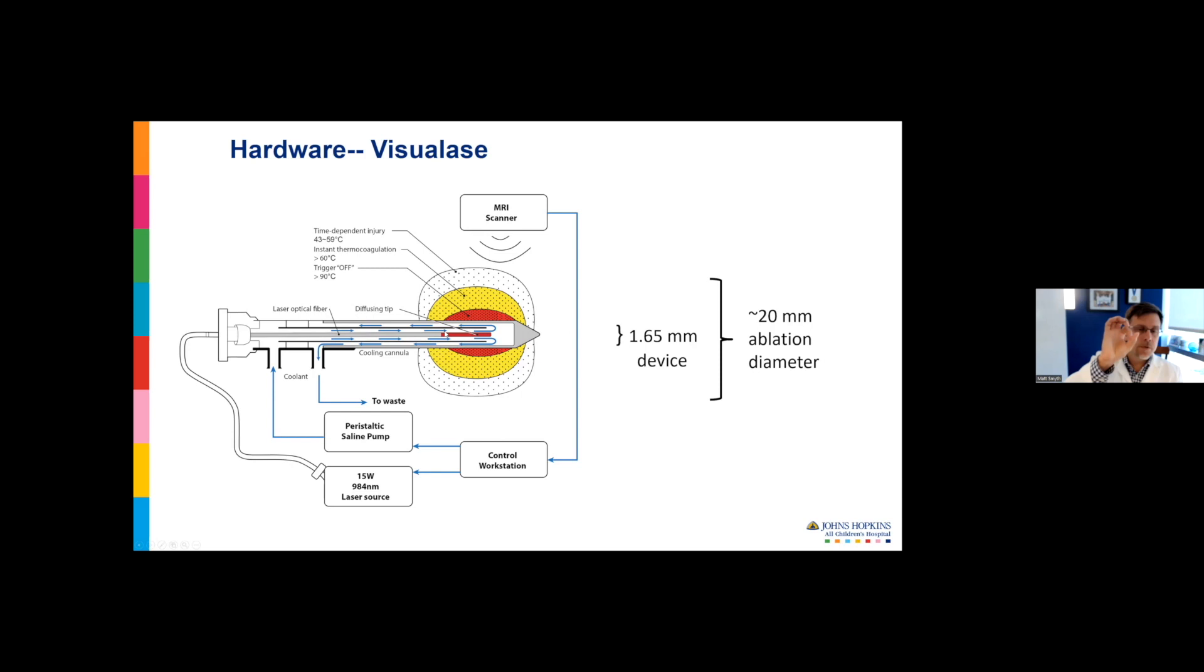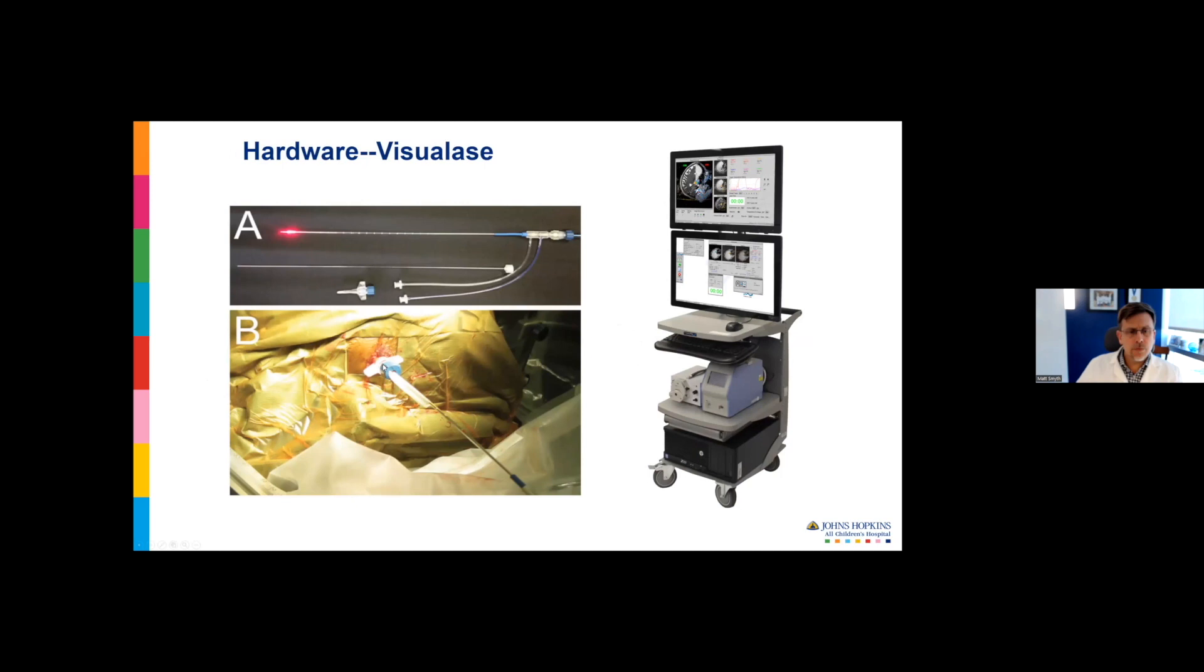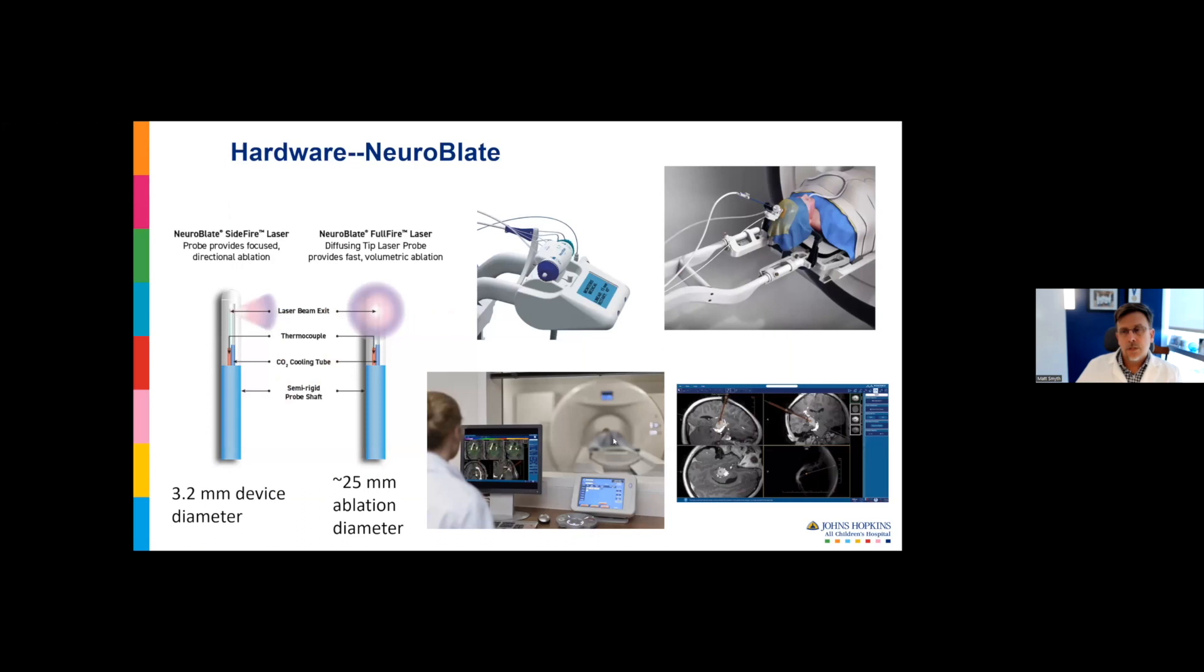The Visualase system is deployed through these MRI compatible bolts, either plastic or titanium. A twist drill is performed along the trajectory of interest, and then the bolt is threaded down into the bone. Through the hollow bolt, you pass the Visualase fiber and secure it in place with this collar. The system is deployed with a cart-based mobile system, which is handy because you don't require a full installation in your MRI scanner.